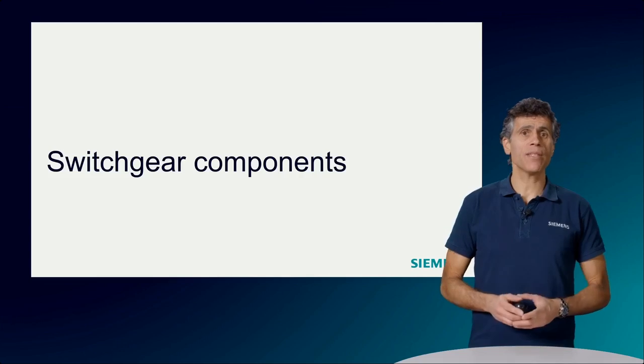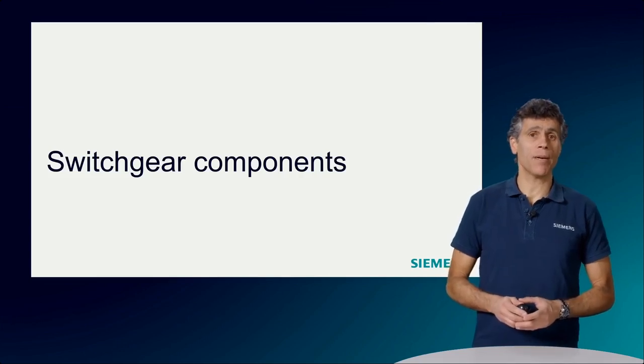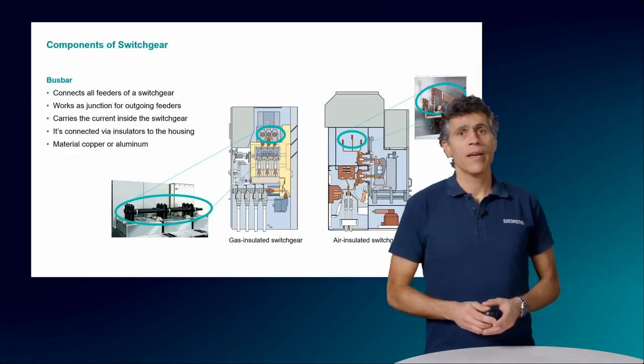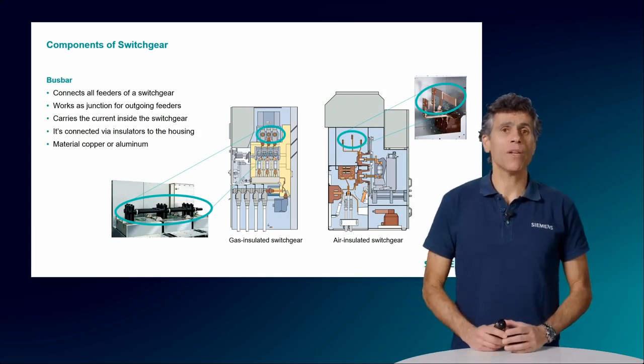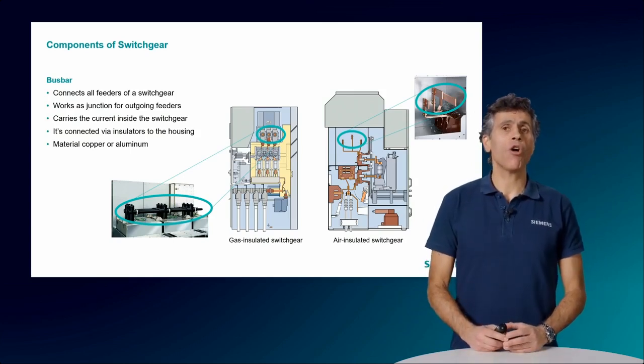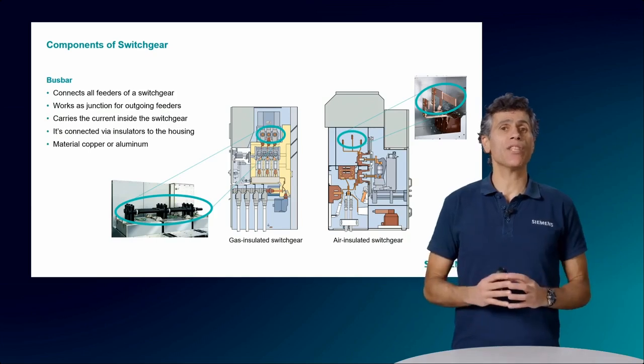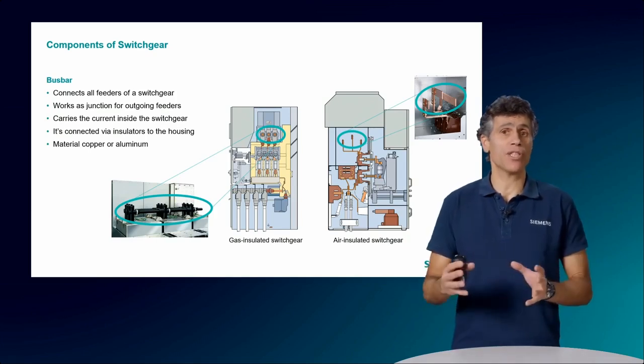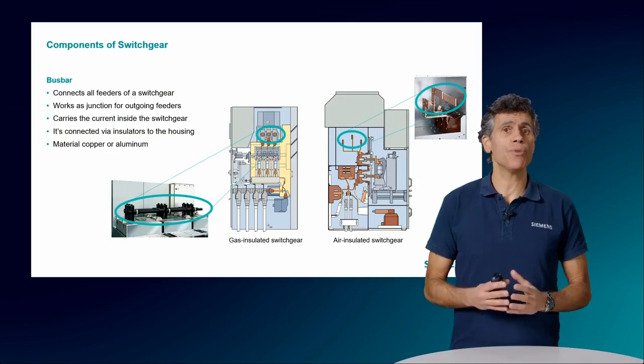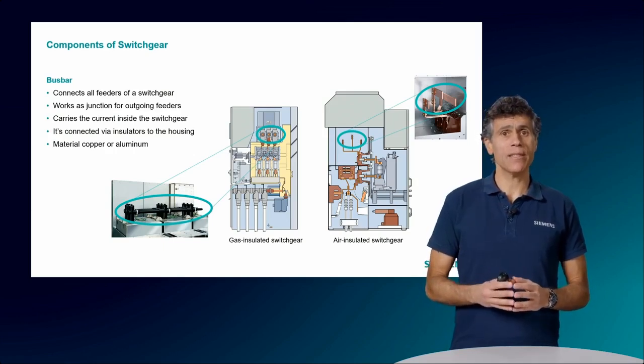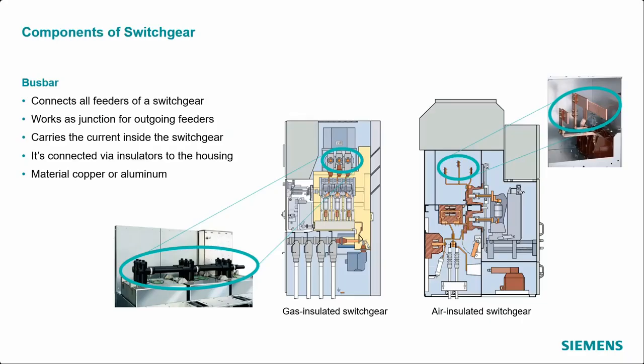The first component that I would like to highlight is the busbar. As mentioned before, the busbar is one of the main elements because it connects all panels together, and this connection is what makes panels into a switchgear. It acts as a distributor center for the electricity. One panel connects it to the network, as I mentioned before, the so-called incomer, and the other panels, usually called outgoing feeders or simply feeders, connect the devices that need electrical power.